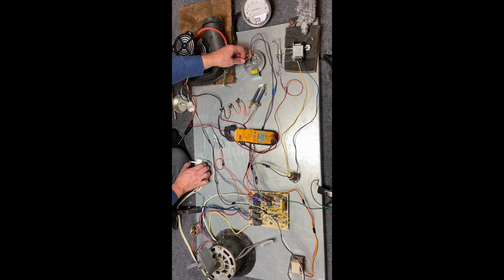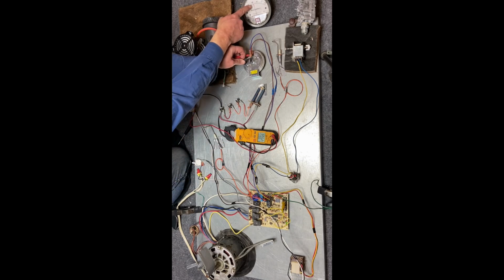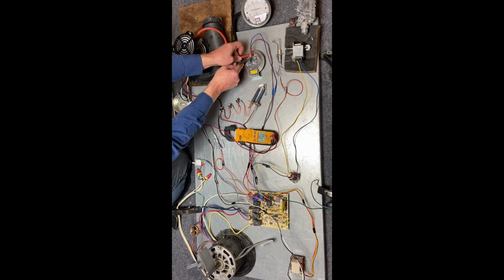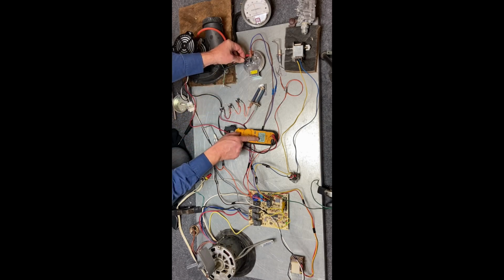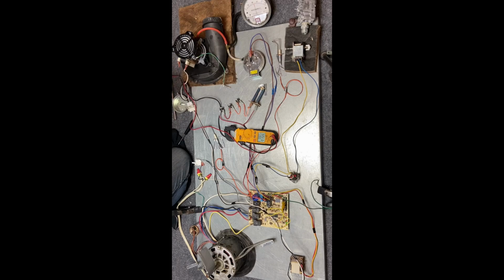And we have a call for heating. I have 27 volts. But once I get enough pressure over here, this switch closes. And when this switch closes, we have 0 volts. So I know that the switch is closed. So it's a 2-part. Do I have this switch closed? And if it's not closed, do I have enough pressure? So if you do have enough pressure and the switch is not closing, you have a bad switch.